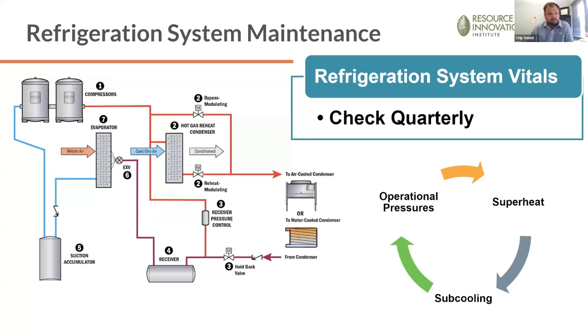Because they're very precise, we need the pressures and the superheat and subcooling of that refrigeration system to be on point if you want the highest level of efficiency and the most dialed-in control. Good news is that's really easy to do when you've got remote monitoring. If you didn't, that would be a much trickier thing to do. It would involve feet on the ground, and I think that would be very difficult.